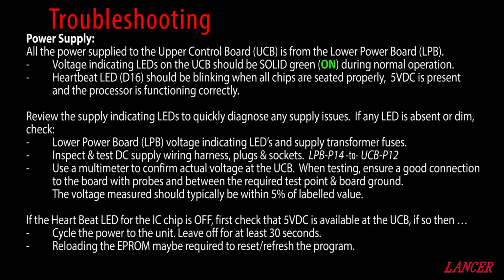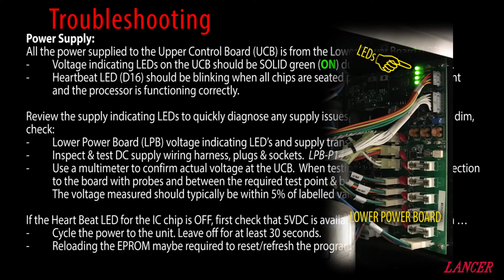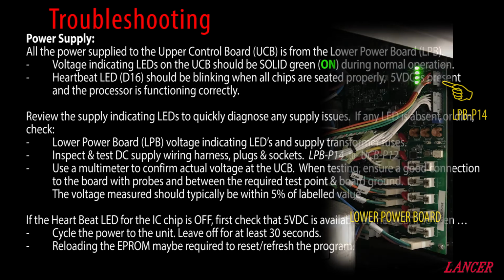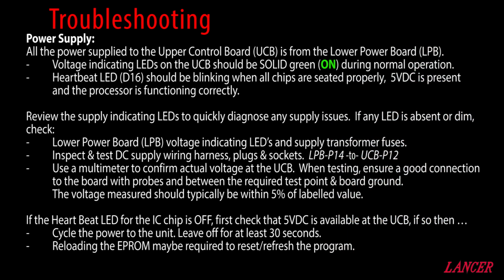If any LED is absent or dim, first check with the lower power board, voltage indicating LEDs and supply transformer fuses. Inspect the DC supply wiring harnesses, plugs and sockets, and then use a multimeter to confirm actual voltage at the upper control board. When testing, ensure a good connection to the board with the probes and between the required test point and board ground. The voltage measured should typically be within 5% of the labelled value.